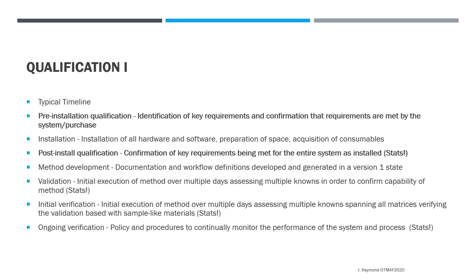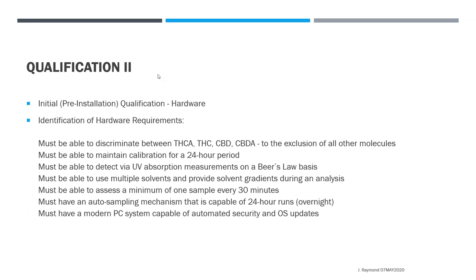Ongoing verification is usually your quality control program. Looking at pre-installation qualification, often people focus exclusively on hardware — and that's important — but to show due diligence as an organization, lab manager, or owner, you want to set your hardware requirements before going to market. You do not want a vendor to guide your requirements. Instead, look at what your customer base needs and what you are saying you're capable of doing in your own laboratory.